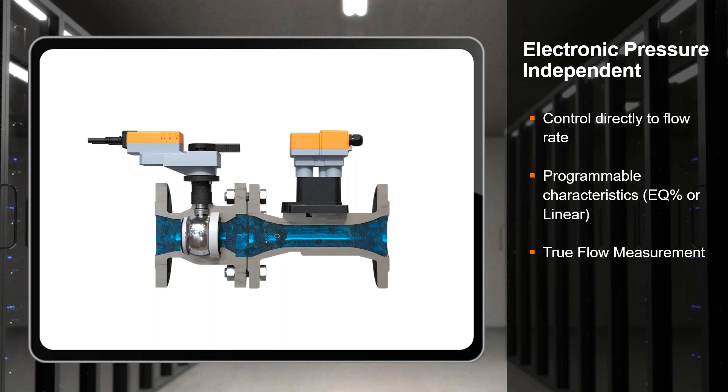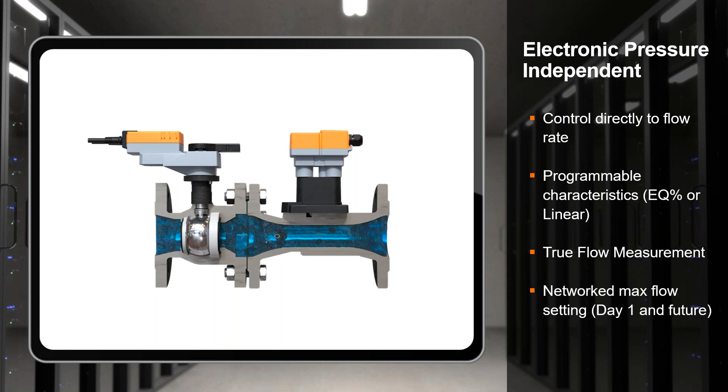Another great advantage is our ability to measure flow. We're measuring it in the system - this is reportable information. Even if you don't network this valve, the analog feedback signal from this valve can measure and report the flow value. So if we've plugged all these valves in and we've run all the feedbacks, we can sit at a single computer terminal and take a look at the flow rates of all of our equipment on all of our racks. We can set alarms if there's disparity between the measured flow rate and the required flow rate and give us so much more information than we can get from simple mechanical devices.